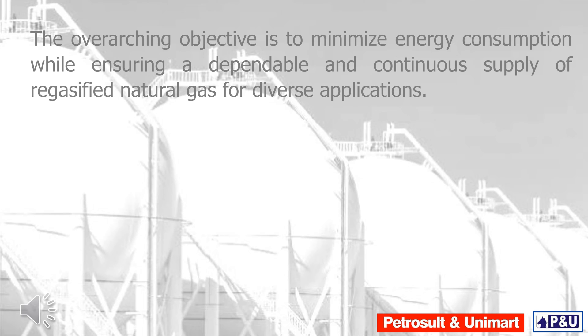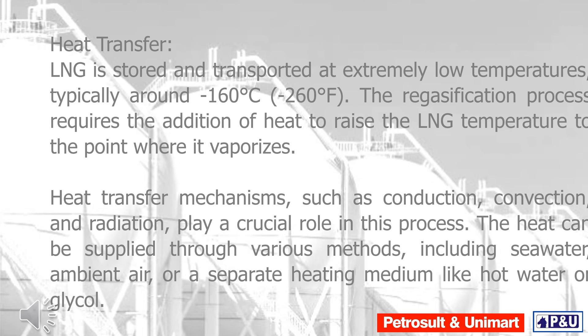LNG is stored and transported at extremely low temperatures, typically around minus 160 degrees Celsius (minus 260 degrees Fahrenheit). The regasification process requires the addition of heat to raise the LNG temperature to the point where it vaporizes. Heat transfer mechanisms such as conduction, convection, and radiation play a crucial role in this process. The heat can be supplied through various methods including seawater, ambient air, or a separate heating medium like hot water or glycol.